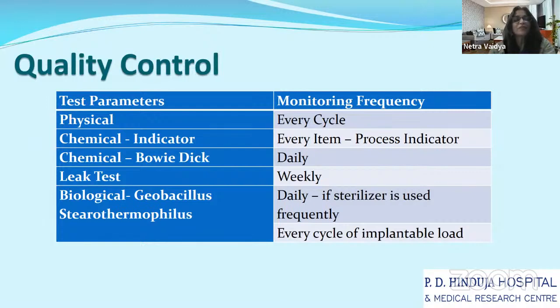And the most important and required is a biological test, which should be done daily if your sterilizer is used frequently, and whenever you have an implantable load processed in your sterilizer, every implantable load should have this. These are the recommendations from CDC, so we must try and follow them. I think that's all I could crisp my presentation into.